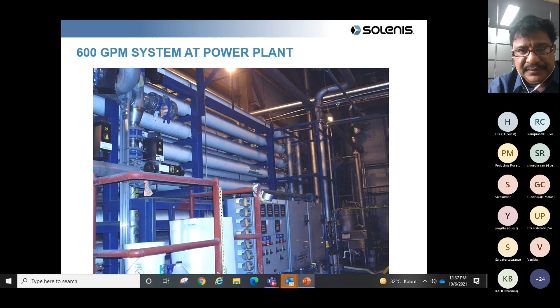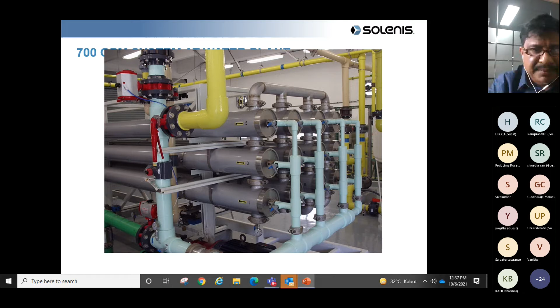Then we have controls on the pH, we have controls on the conductivity, we have a lot of interlocks. Whenever the pressure is high, the reject valve will automatically open so that it drains and does not pass the pressure, because we have come across many membranes getting damaged due to maloperations. So this is a simple RO plant, and these are the membranes, as you can see, the pressure tubes.